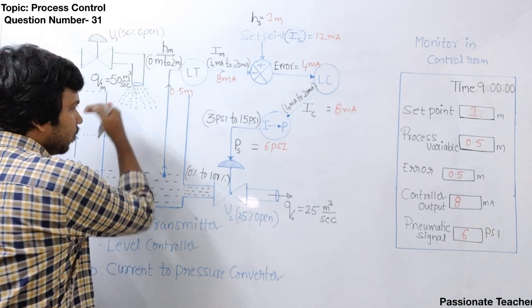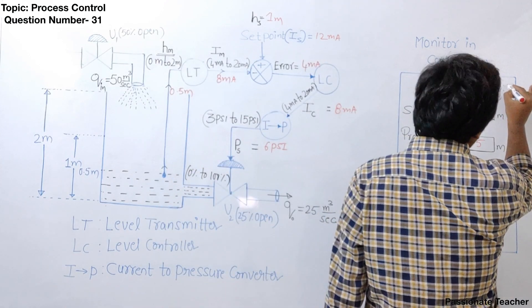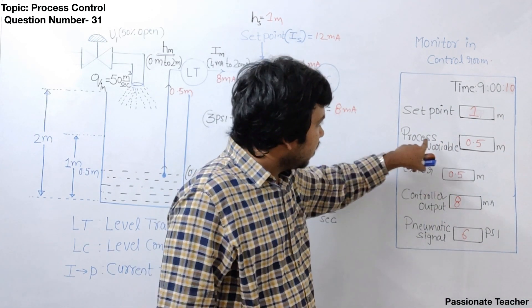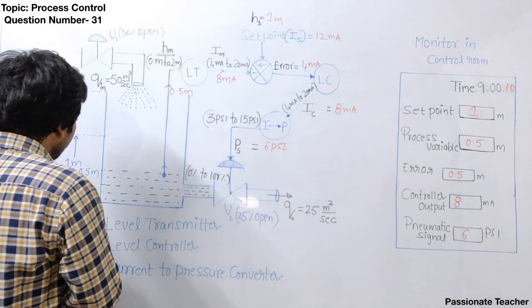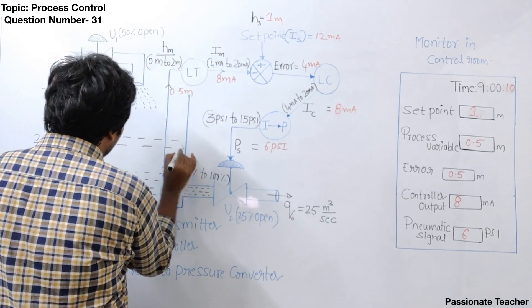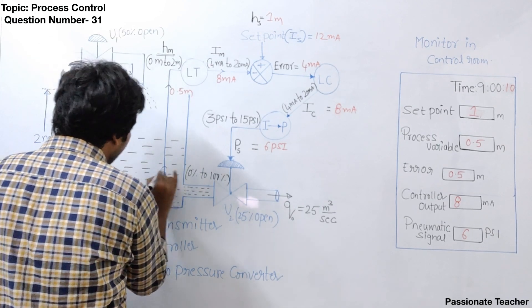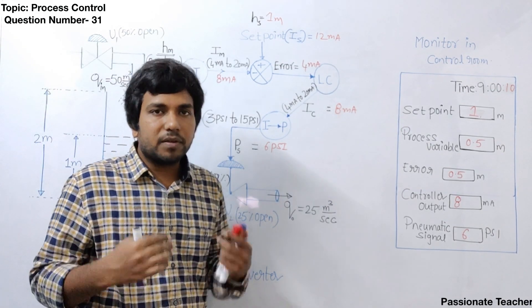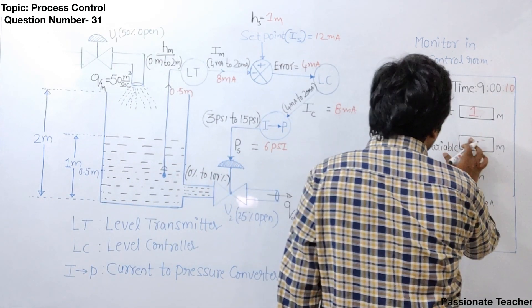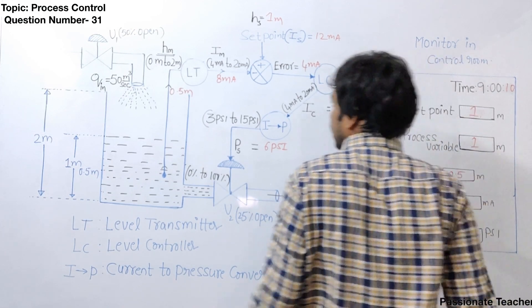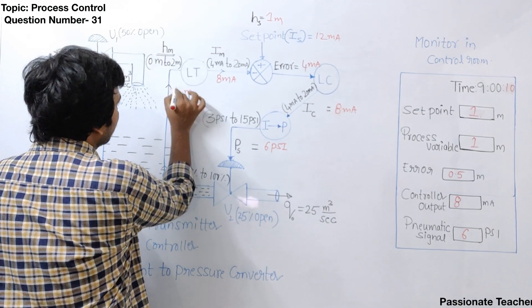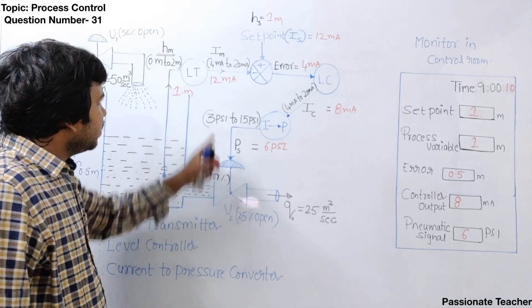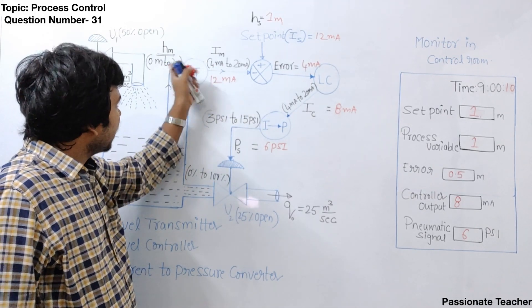If we wait for 10 seconds, the setpoint remains unchanged but the process variable will slowly change. Let's say after 10 seconds the process variable reaches 1 meter. Whether it reaches 1 meter in 10 seconds depends on many factors such as the cross-sectional area of the tank and the resistance of the valves. Assuming the water level reaches 1 meter after 10 seconds, the level transmitter will generate a current proportional to this water level — which will be 12 milliampere.